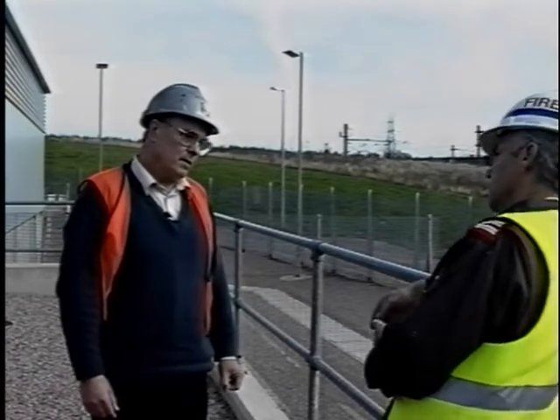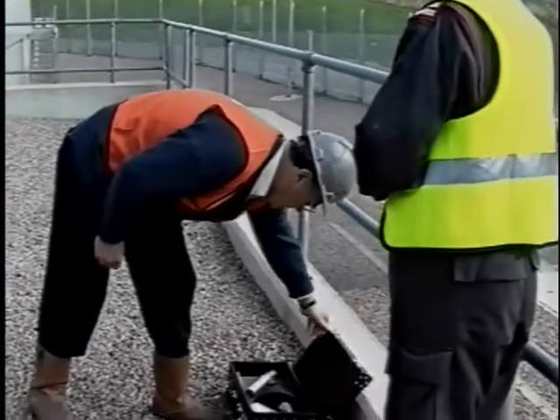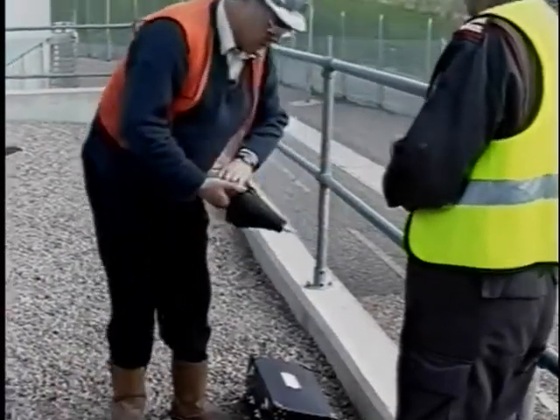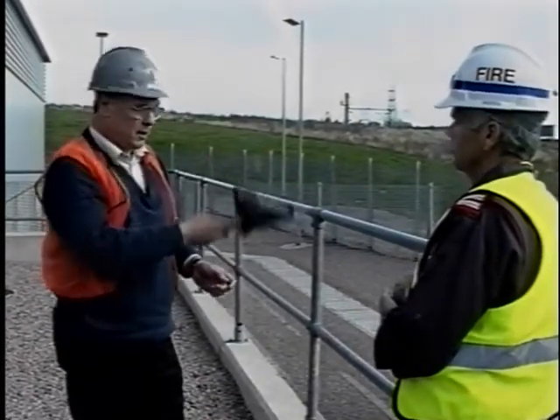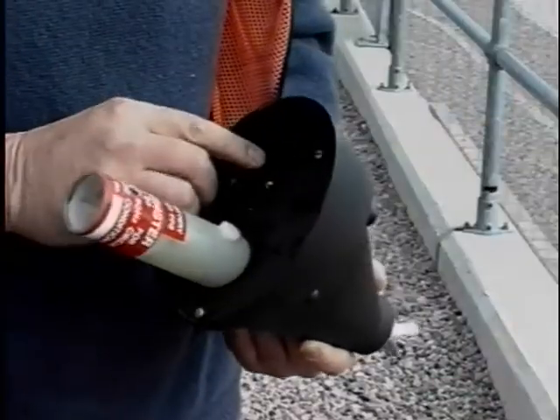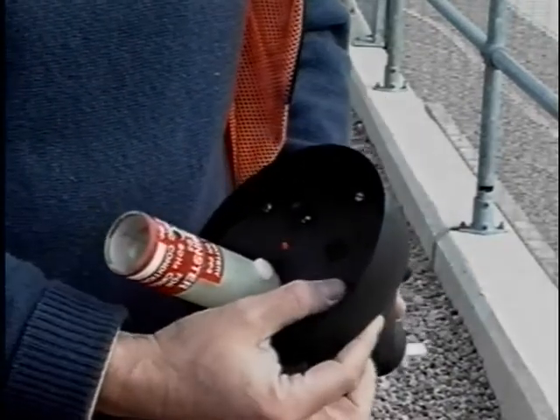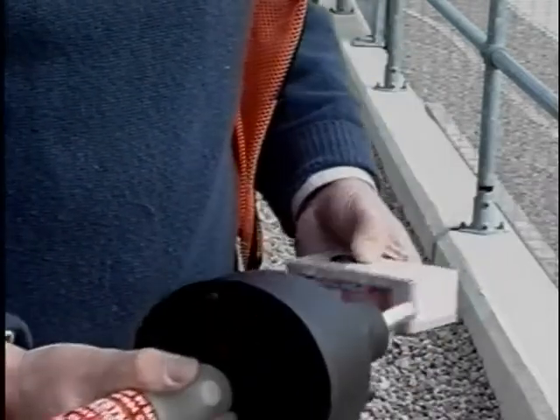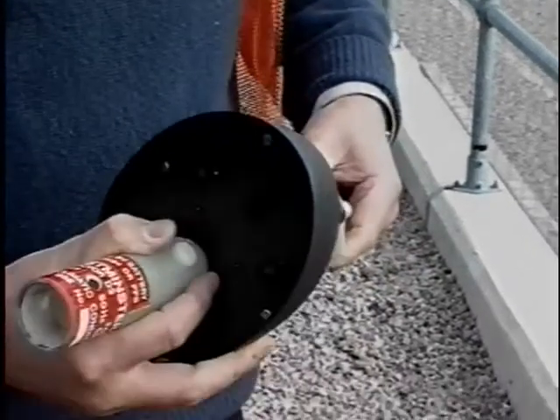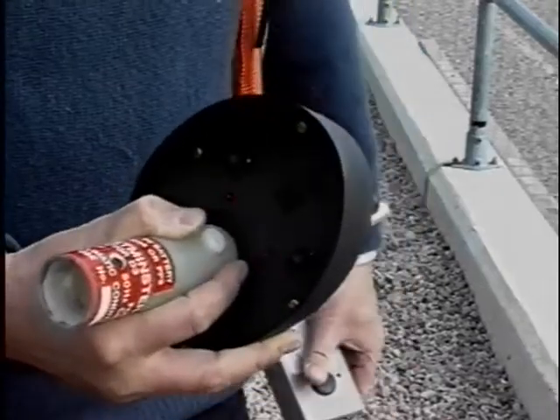You've got one of those live line testers here, Eric. Could you show us, so we can recognise what one of these things does? Right, what we've got is this, which will fit on the end of our poles, so we could actually go up onto the catenary system. Basically, you switch it on, which gives out a bleeping. We've got a test facility on it, which we prove and then it gives a continuous signal. And then we have what they call a proving unit, which you hook onto the end of it, and it will simulate a voltage present.